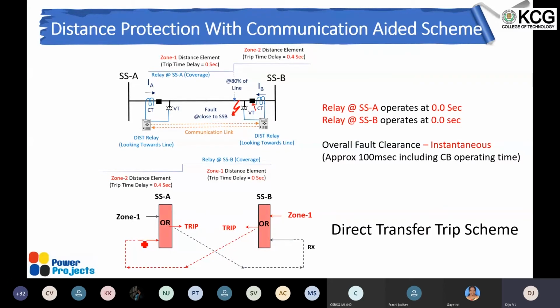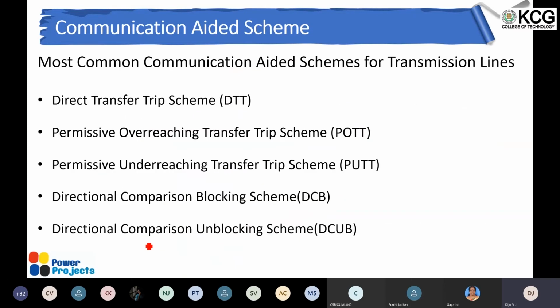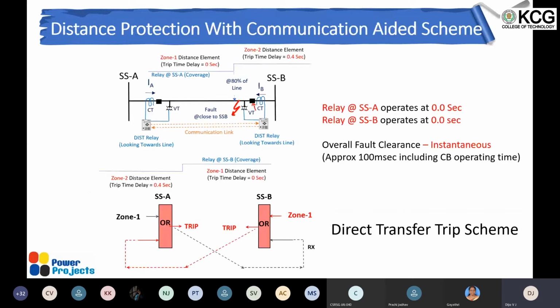So this tripping scheme is called the direct transfer tripping scheme, and the communication part is very important here. So that's the main protection requirement with respect to the communication point of view. One is the differential, and another one is the distance with communication aided tripping schemes. We call it by different names. Sometimes we call it a communication aided tripping scheme, sometimes a carrier aided tripping scheme, like that.